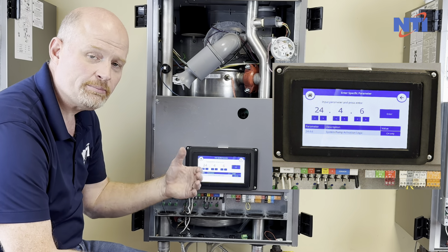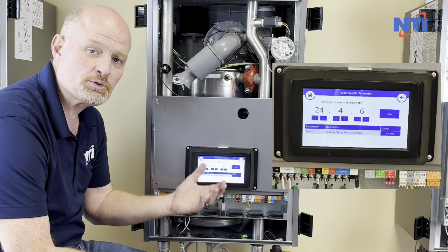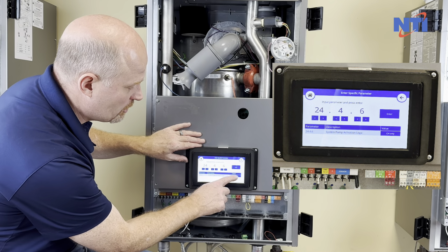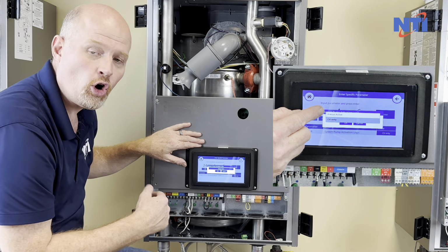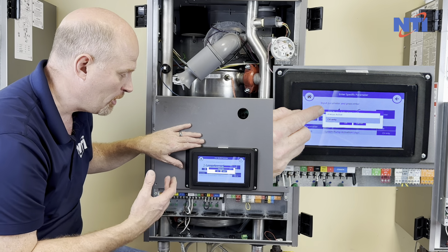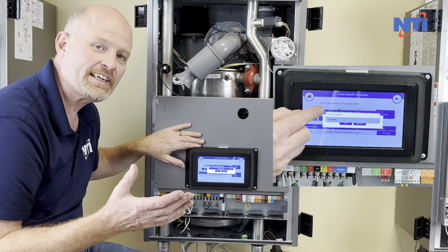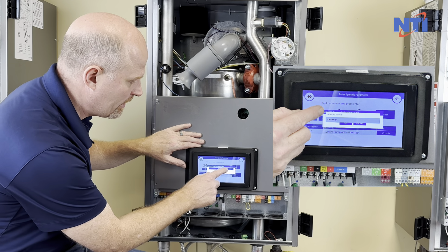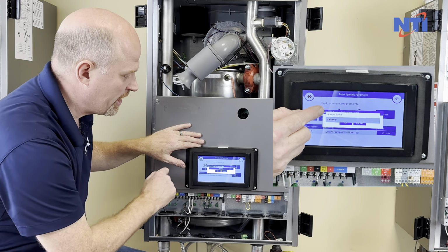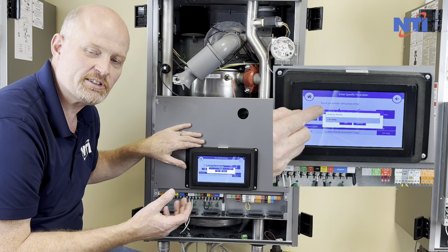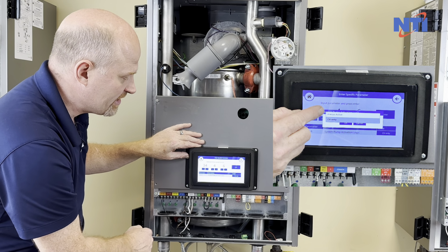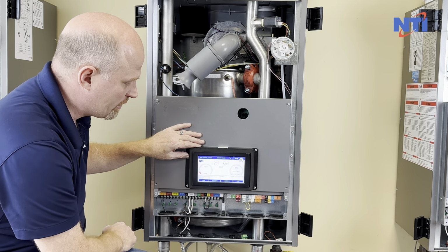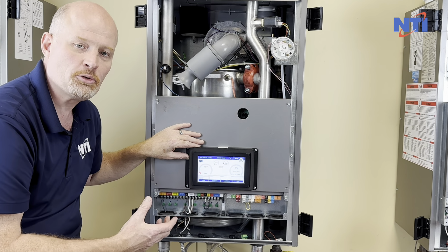So if you have a system pump that is required to run for central heat and domestic, you want to come to this menu, touch this, and change it so it's always active. Always active doesn't mean running all the time. It means it's active for central heating and domestic. If we touch that again, we'll change it to CH only, and that means this pump will shut off during your domestic hot water call. Press OK to save your setting, and then you can hit the home button, and you've now set your pumps.